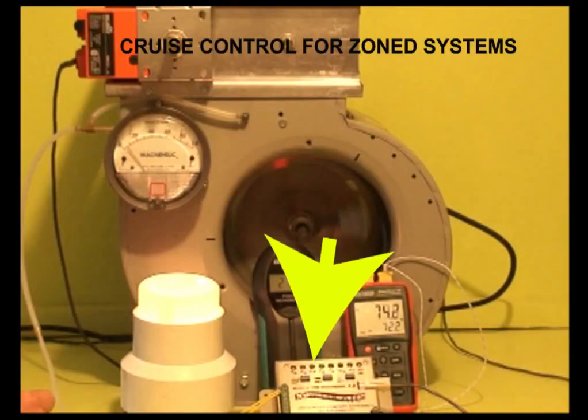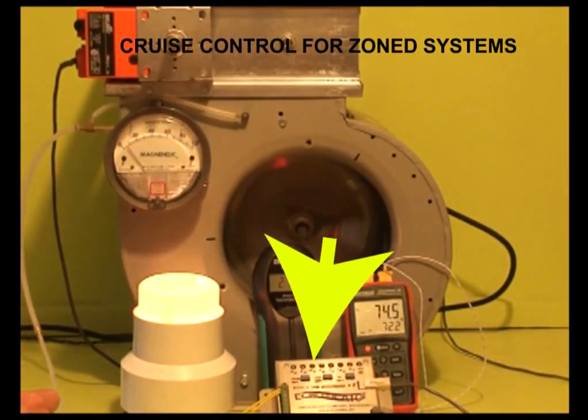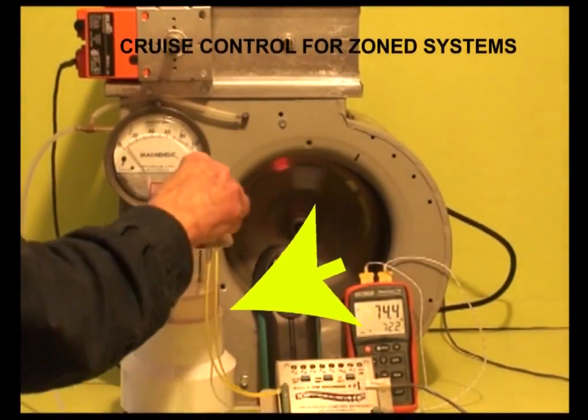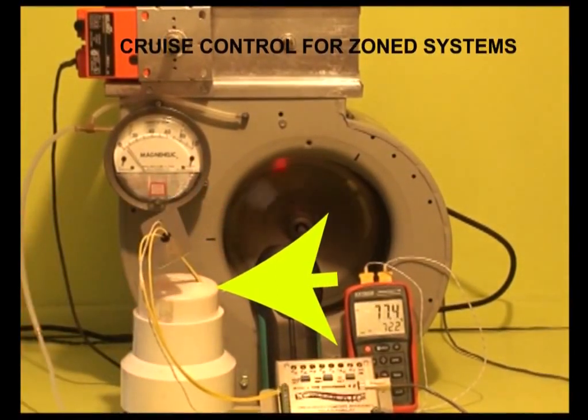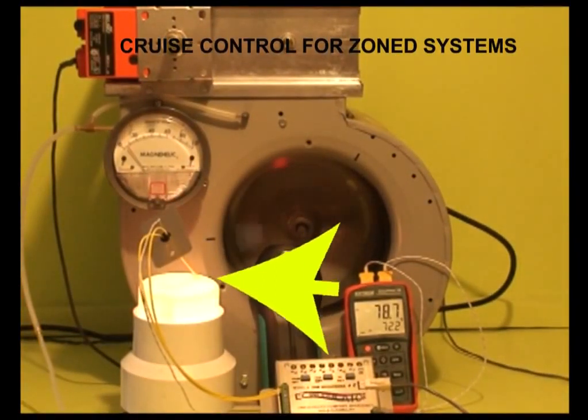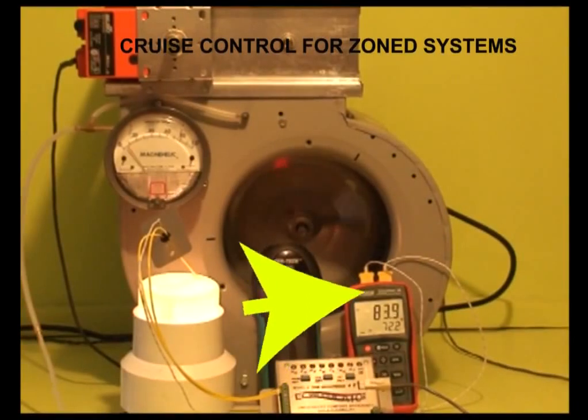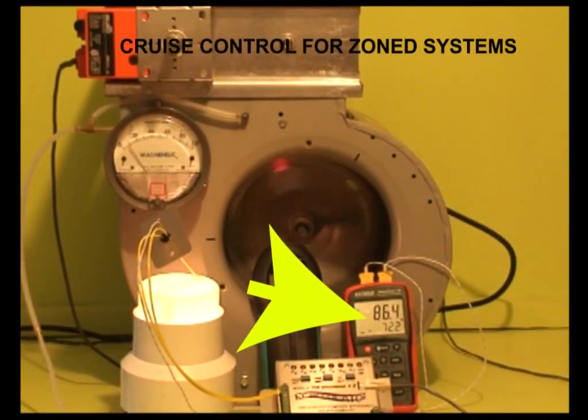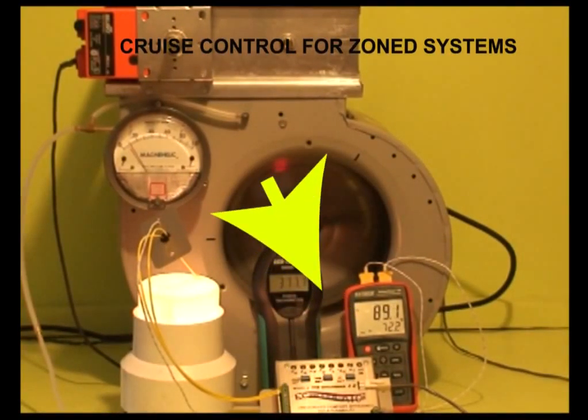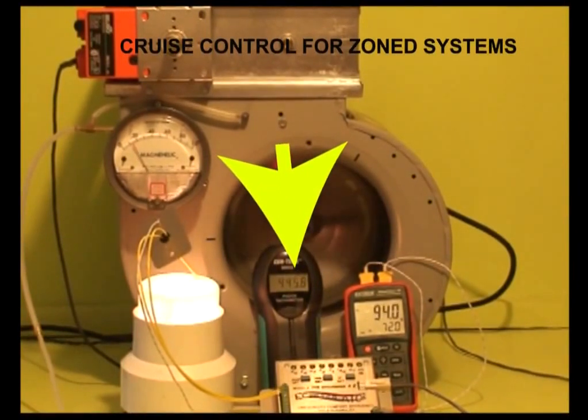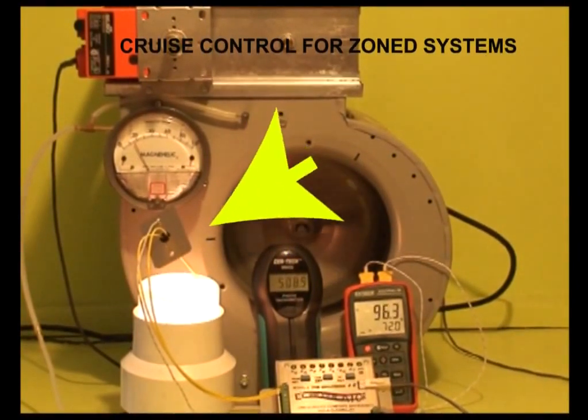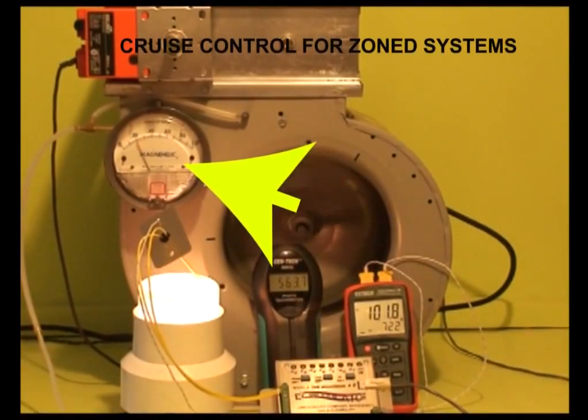This is the ECM modulator control. It modulates the speed of the blower in response to discharge air temperature at the sensor, which is shown being heated by a light. This is a digital thermometer that shows the temperature at the sensor. This is a digital tachometer that shows the blower's RPM. This is a magnehelic that shows the duct pressure.